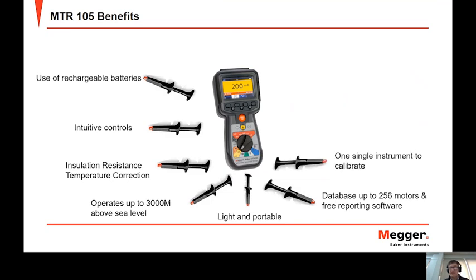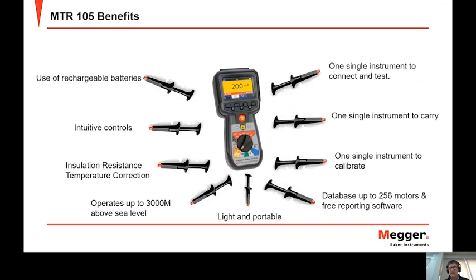Another benefit is you have one single instrument to calibrate each year instead of 6 or 7 units. So you have a cost saving and also a time saving. We have one single instrument to carry to site or around the workshop instead of multiple units. So did we forget one of the units when we went to site? Do we have the right leads with it? The MTR includes everything in its little carry case, so nothing is forgotten. And we have one single instrument to connect and test with, so we save time when we're testing, and we are much more professional.